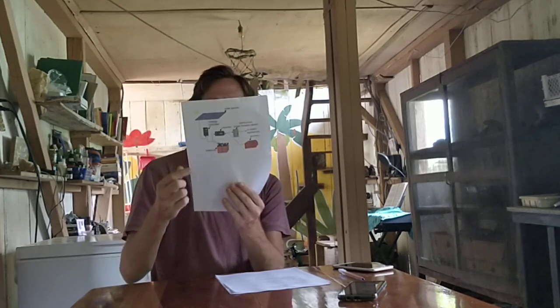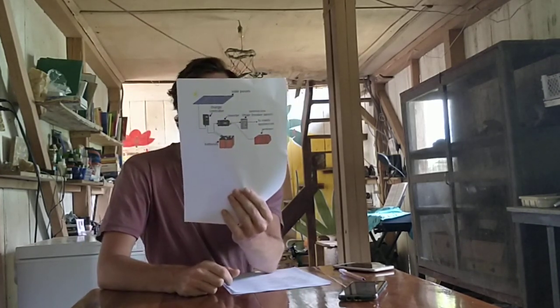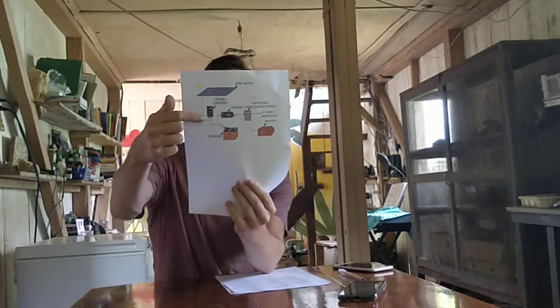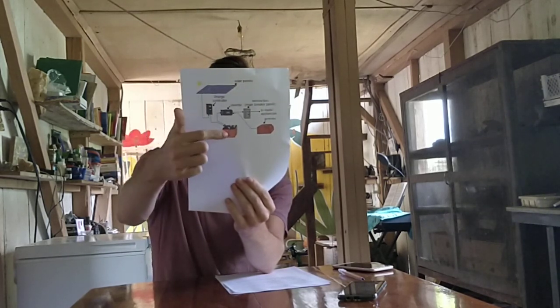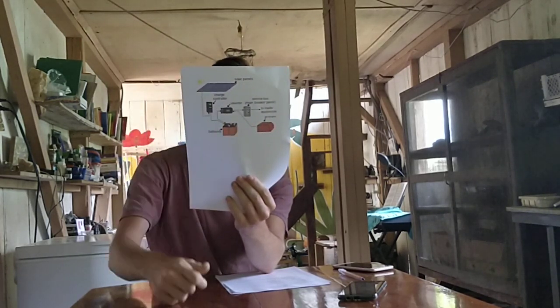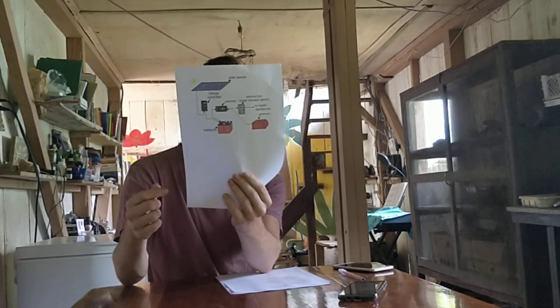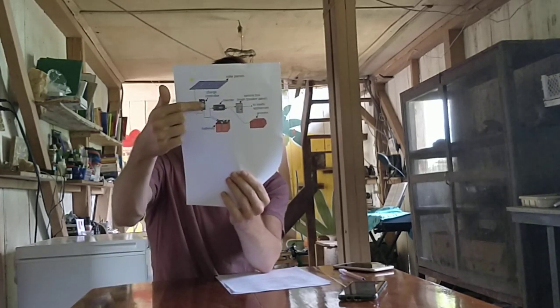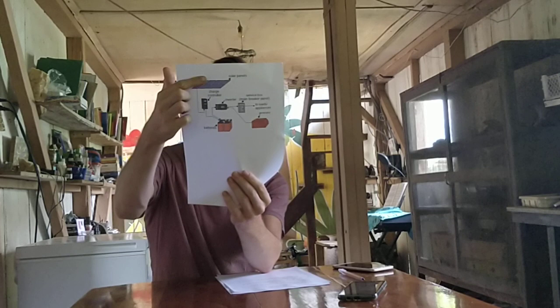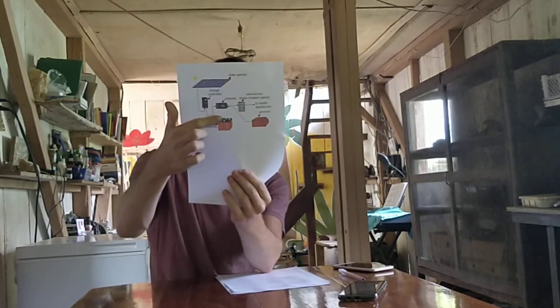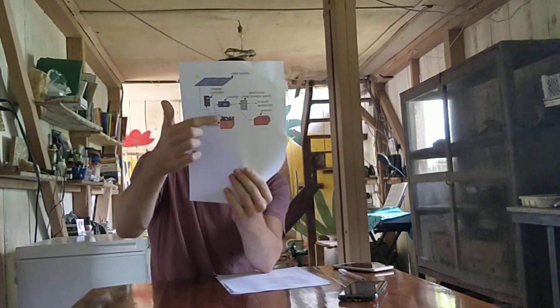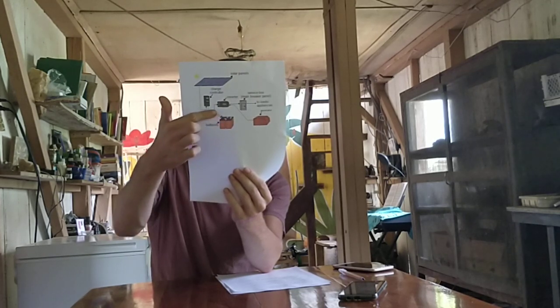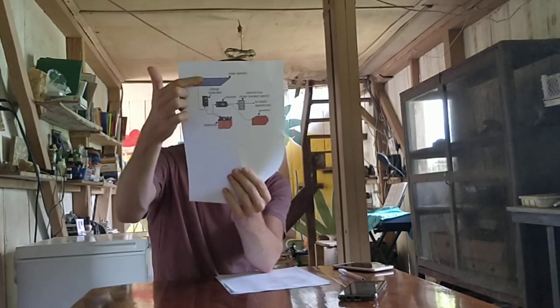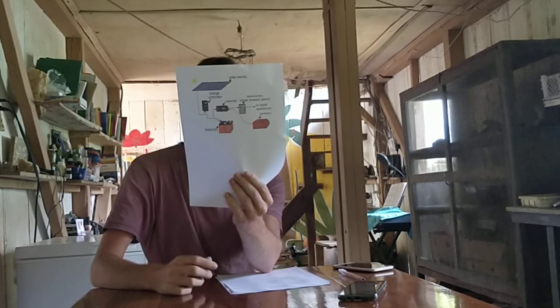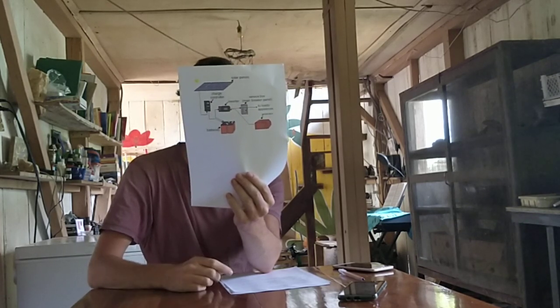To have a really safe system, you also need a fuse or circuit breaker between the panels and the charge controller, and also after the batteries. This prevents issues if your charge controller malfunctions. For example, solar panels can charge the batteries fully, and once they're full, current can start flowing the other direction. You don't want your batteries charging your solar panels, because the panels would be ruined very quickly, totally destroyed.